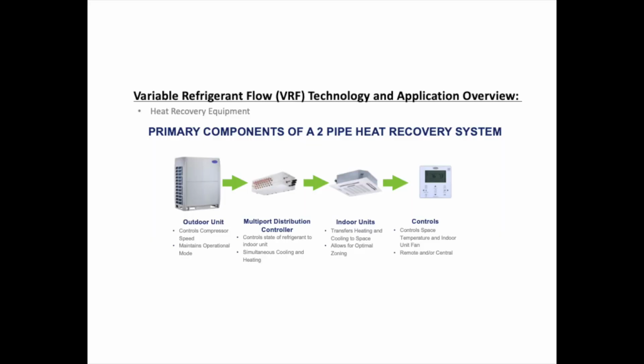Let's look at the primary components for a two-pipe heat recovery system. It's very similar to a heat pump system where you have your outdoor units, you have your indoor fan coils, and you have your controls. But we also introduce another piece of hardware called the multi-port distribution controller. And this is what controls the state of the refrigerant going from the outdoor unit to the indoor unit. And this is what allows for simultaneous heating and cooling.